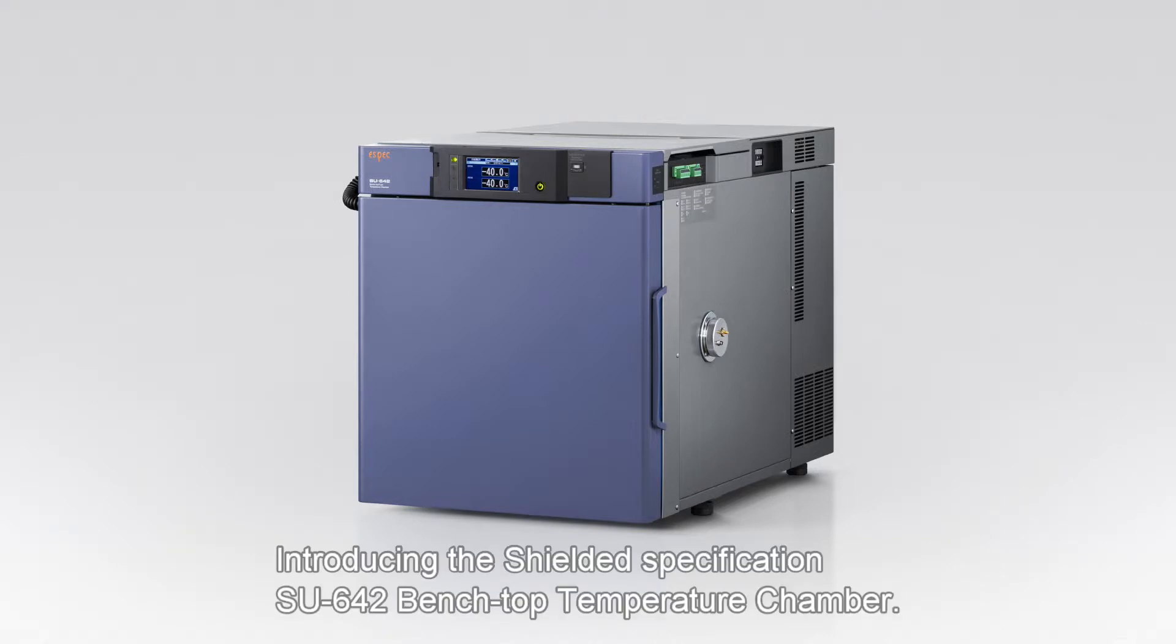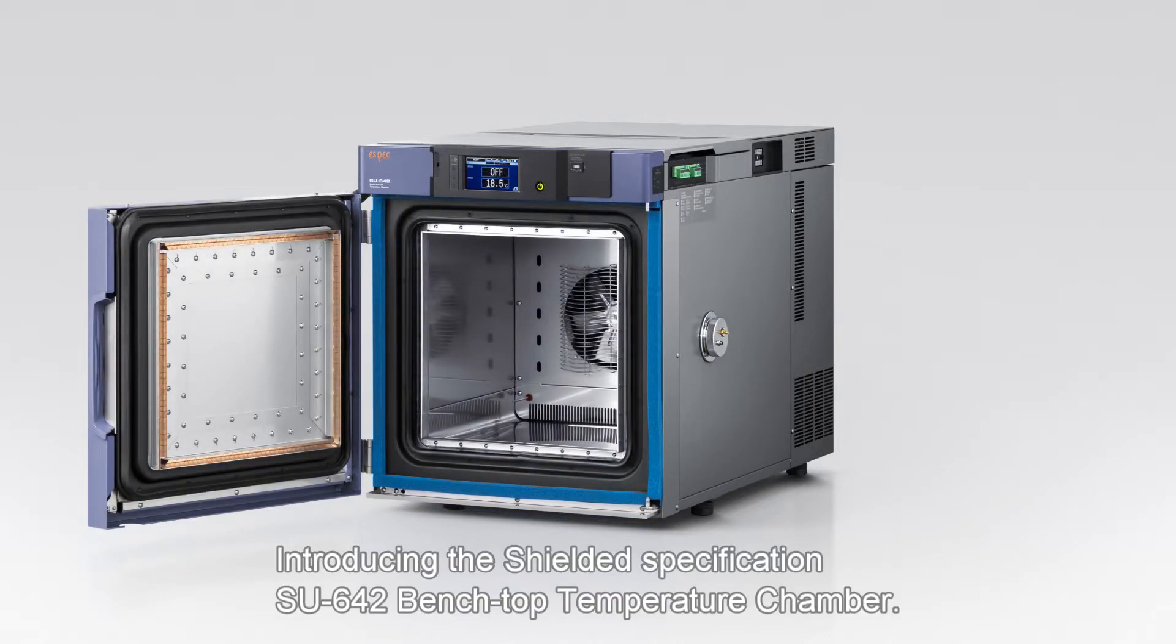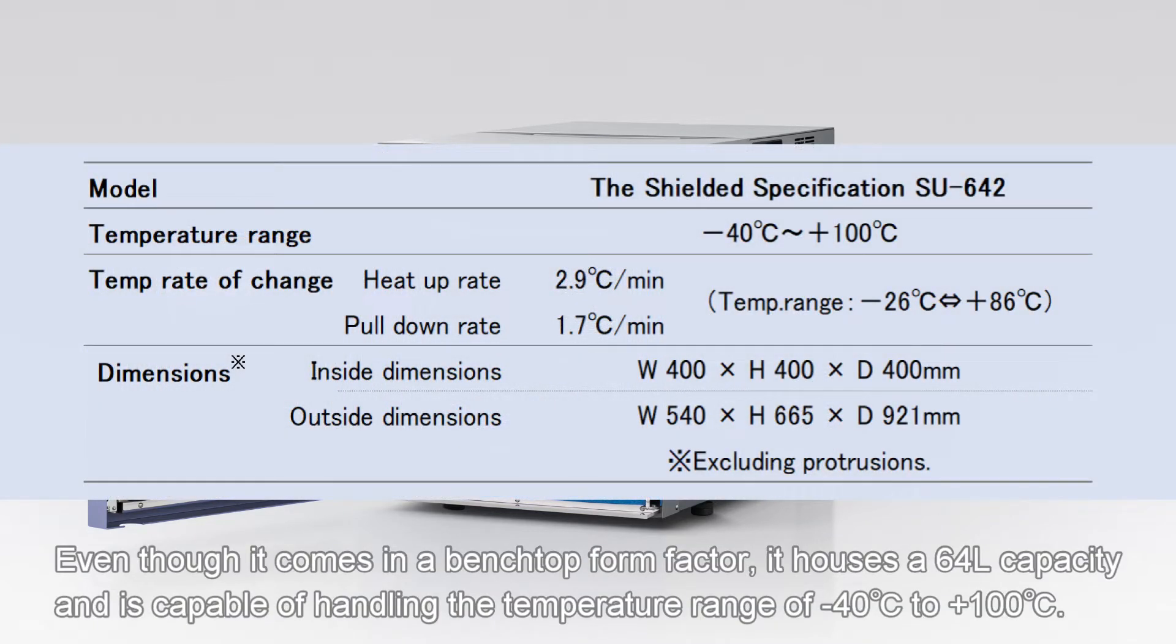Introducing the Shielded Specification SU-642 Benchtop Temperature Chamber. Even though it comes in a benchtop form factor, it houses a 64-liter capacity and is capable of handling the temperature range of minus 40 to plus 100 degrees Celsius.